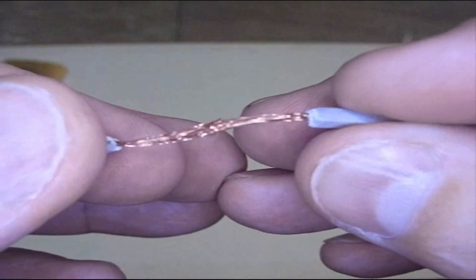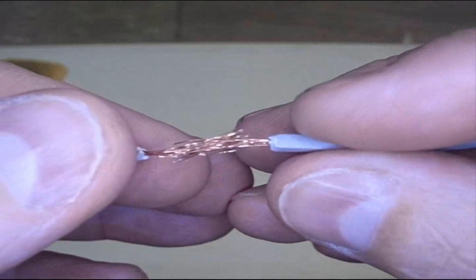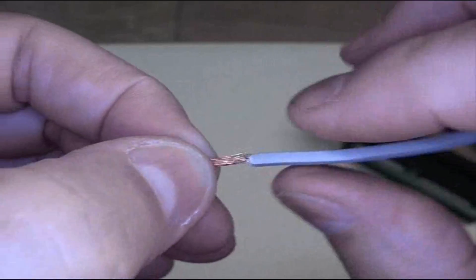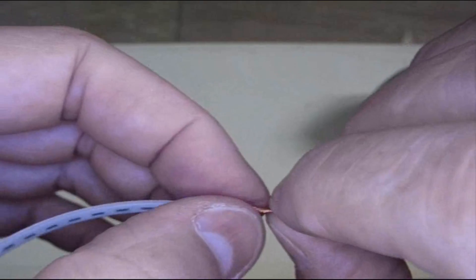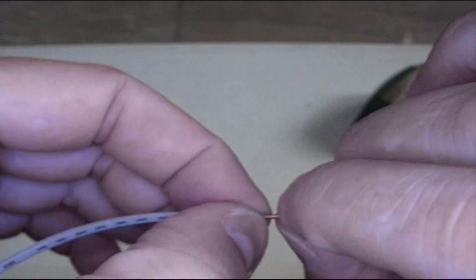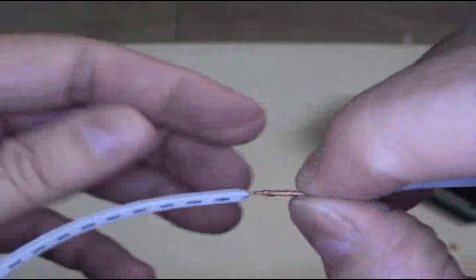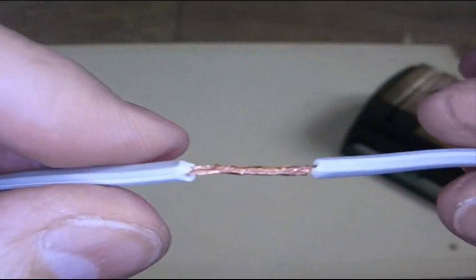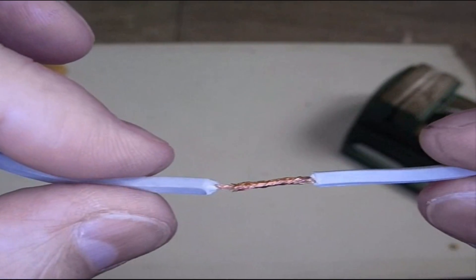Another technique is to push the wires together like this. I think they call it an X splice. Then to twist it like this to make it mechanically secure. This is a lot more difficult with heavier duty wire I can tell you. Like that. You have a relatively good mechanically secure splice.